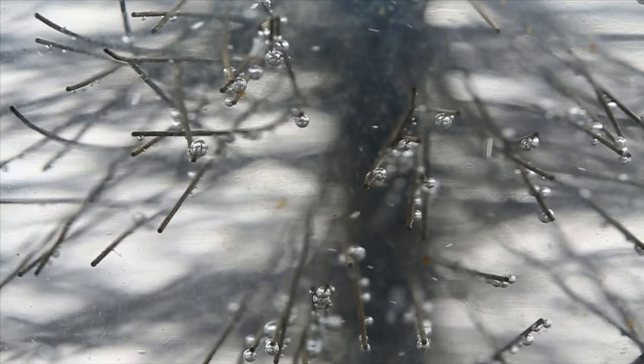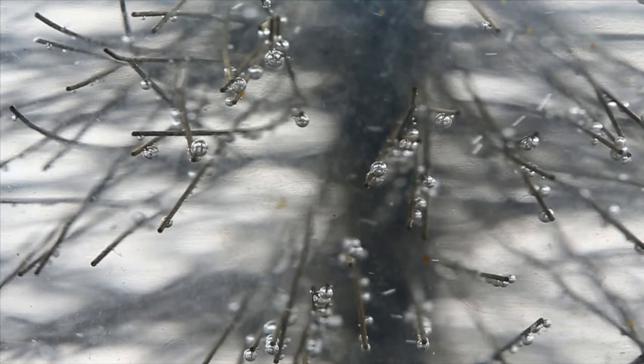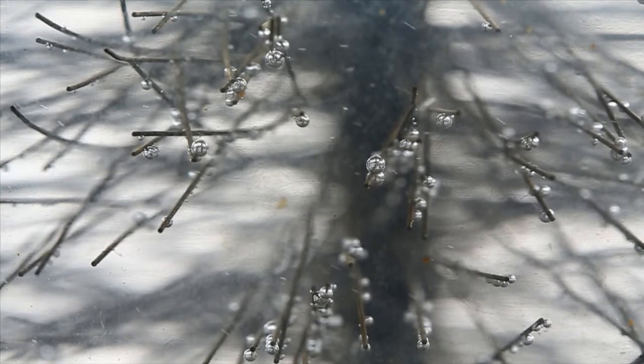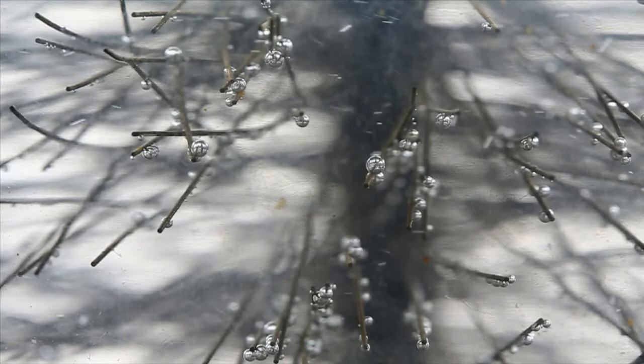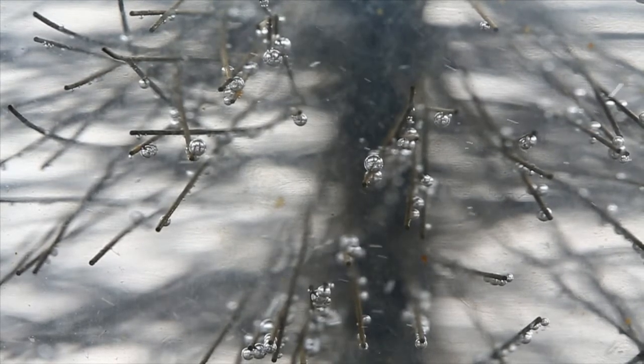Look carefully and see the smallest of micro-bubbles being collected by the filter's fine wires. They all then rise steadily to the top, collecting other micro-bubbles along the way, increasing in size. This is also known as coalescing.